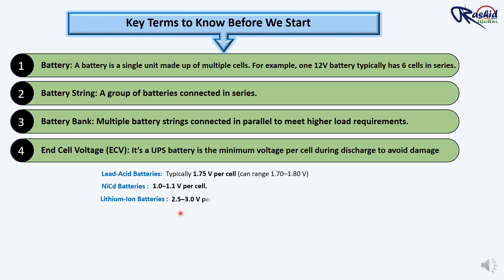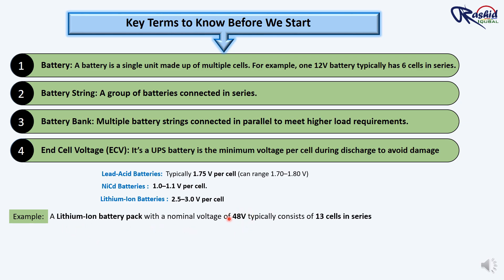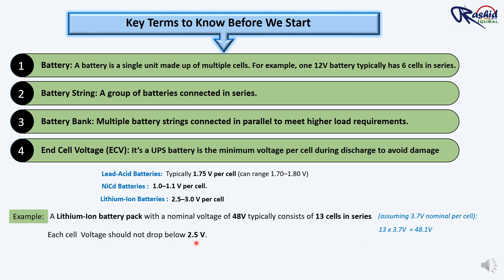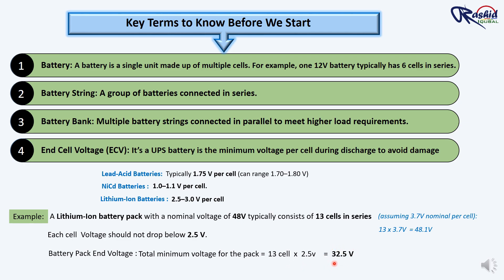Lithium-ion batteries have an end cell voltage of 2.5V to 3V per cell. For example, a lithium-ion battery pack with a nominal voltage of 48V typically consists of 13 cells in series, each with a nominal voltage of 3.7V. Total nominal voltage: 13 × 3.7V = 48.1V. Each cell voltage should not drop below 2.5V — this is the end cell voltage. So the total minimum pack voltage equals 13 × 2.5V = 32.5V.